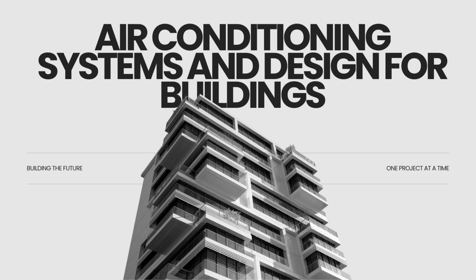A ton of refrigeration, or TR, what exactly is that? It's a standard unit of cooling capacity, particularly common in North America and in commercial HVAC contexts. It's defined as the rate of heat transfer required to produce 1 short ton, which is 2,000 pounds of ice, at 0 degrees C from water at 0 degrees C in 24 hours. In more practical terms we use today, 1 TR is equivalent to removing 12,000 BTUs per hour. Okay, so 1 TR equals 12,000 BTU. That helps connect it back.